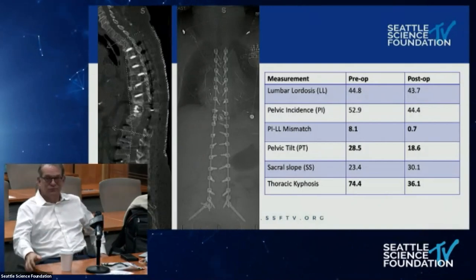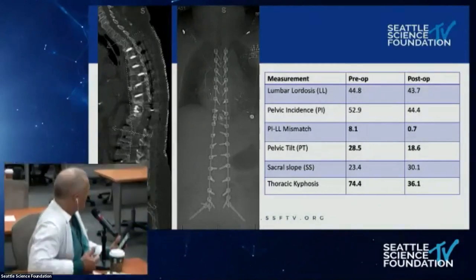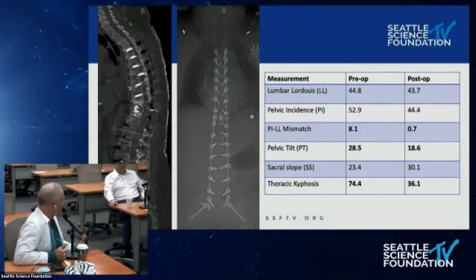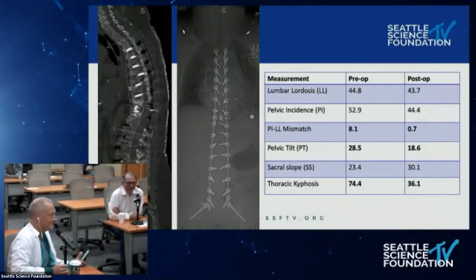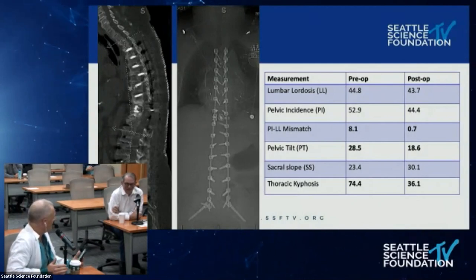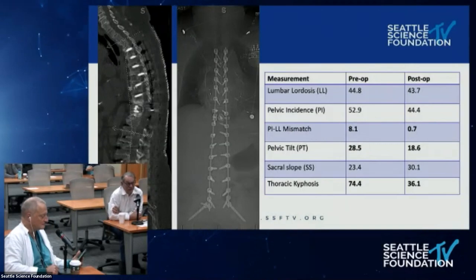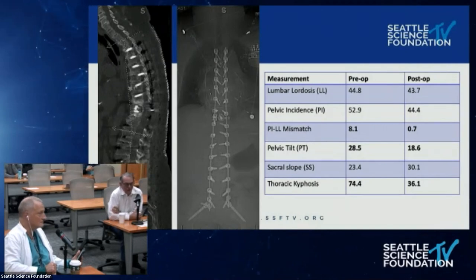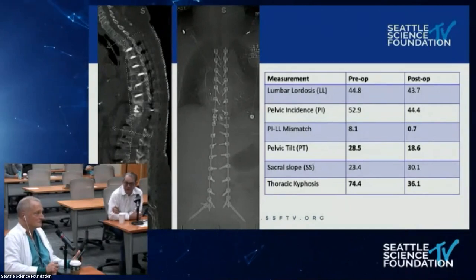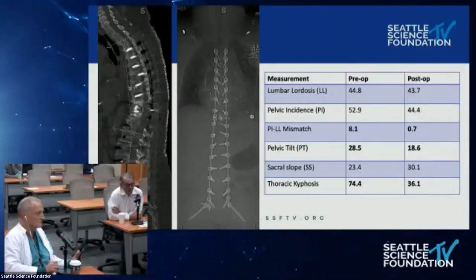Chapman asks which material is most notch sensitive when bending rods. Hart notes this is a great question — all material tests have been done with straight rods, not bent ones. When using French benders, notching is created. Titanium is very notch sensitive. There's definitely notching with any bender used. We're entering an era of patient-specific pre-contoured rods — already available, recently added to contract at their institution — which are contoured without notching.